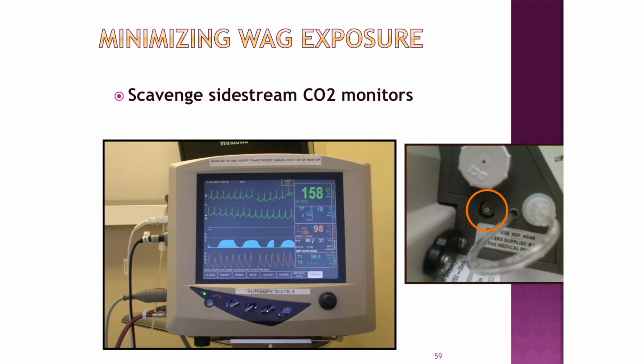They're very good machines. One thing I did want to mention about the SurgiVet machines is that they do collect carbon dioxide and waste gases in order to read this carbon dioxide waveform. And if you look at the side of the SurgiVet, you can see there's a small hole right here. And this is where the waste anesthetic gases and carbon dioxide sample are ejected from the SurgiVet machine.